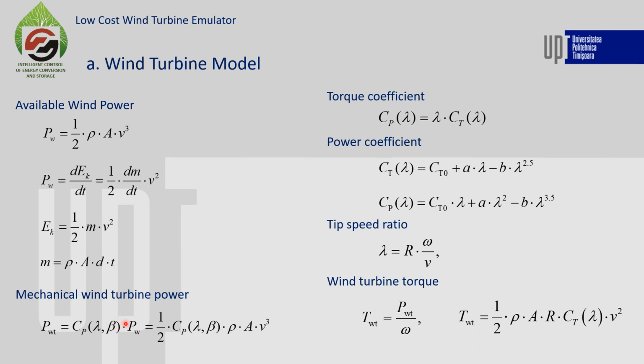Considering this, at each moment the speed ratio can be calculated by this equation, where R represents the radius of the circle traced by the turbine blades, omega is the shaft speed, and V is the wind speed. The power coefficient is related to the torque coefficient, as you can see.